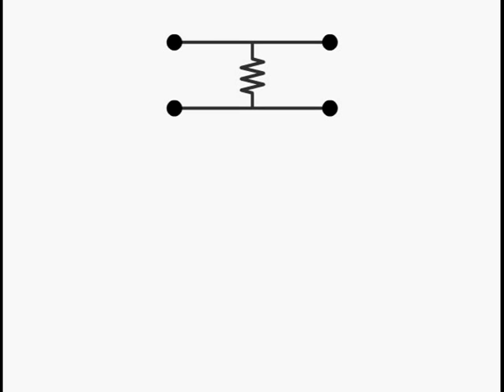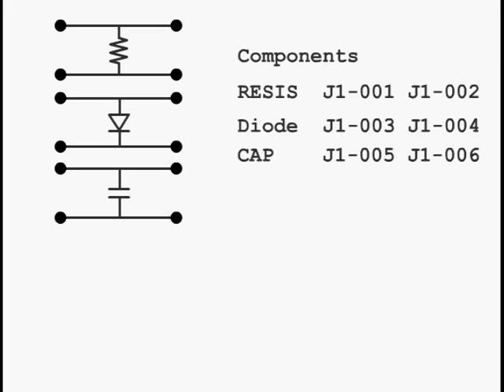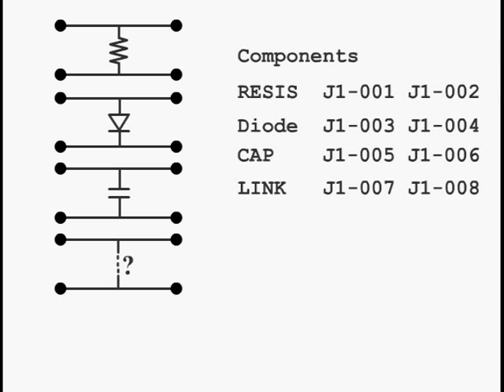Nets connected through resistors, diodes, and capacitors are automatically linked together this way to avoid being damaged. You can also add a link command anywhere in a test program to link together any nets or points between which you don't ever want high voltage applied.